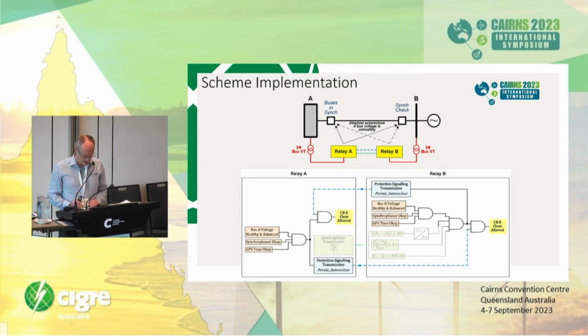Following a fault clearance and at the end of the auto-reclose open interval, circuit breaker A will close if the voltage is still healthy and balanced and it has received a permit auto-reclose from relay B. Similarly, at the end of the auto-reclose open interval, circuit breaker B will close if synchronism check conditions are met, bus B voltage is still healthy and balanced, and it receives a permit auto-reclose from A. System studies can be used to adjust the open interval and take account of transient voltages and swings.